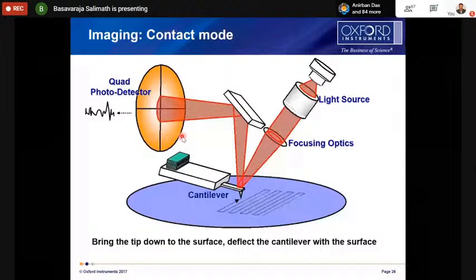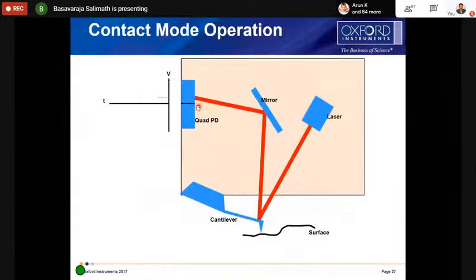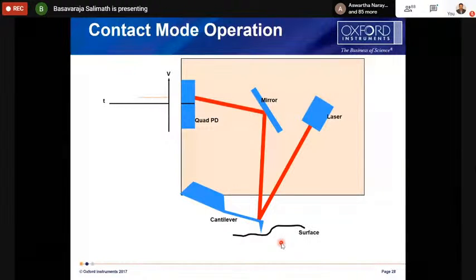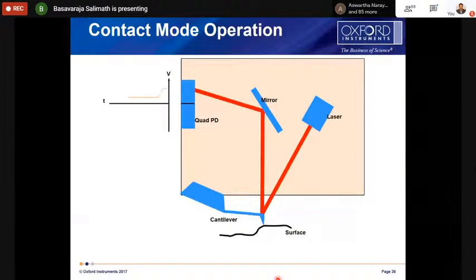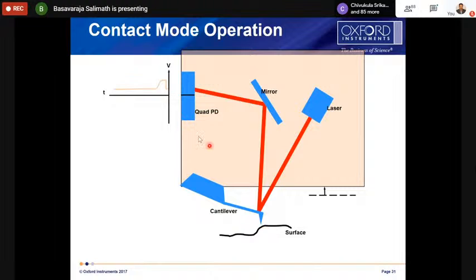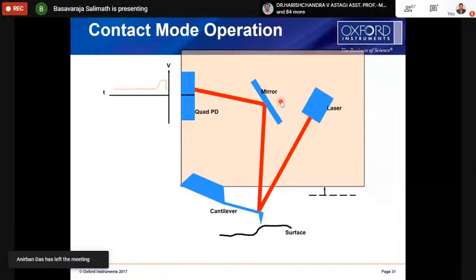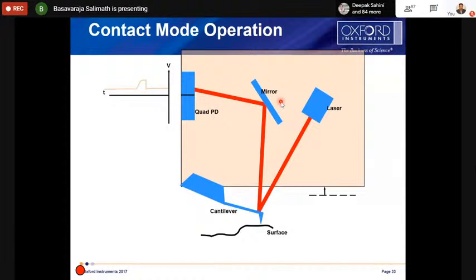Like you can see, this is your surface, and initially the reflected laser in the photodetector is at this place. When the tip goes up, the reflected laser also goes up, but it has to be maintained constant at the original position. So the feedback will adjust the cantilever Z height, and then it comes back to this position. You can see this height is adjusted and now it came back to the original position. So like this, it is scanning the surface in the case of contact mode.